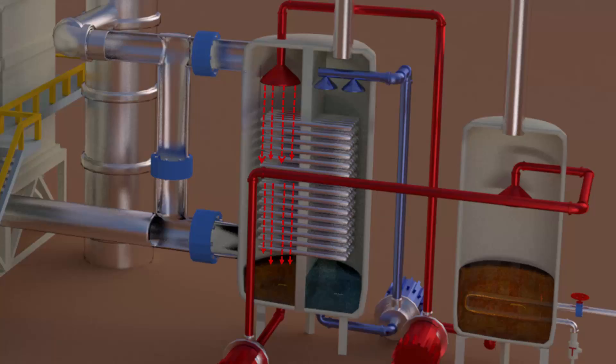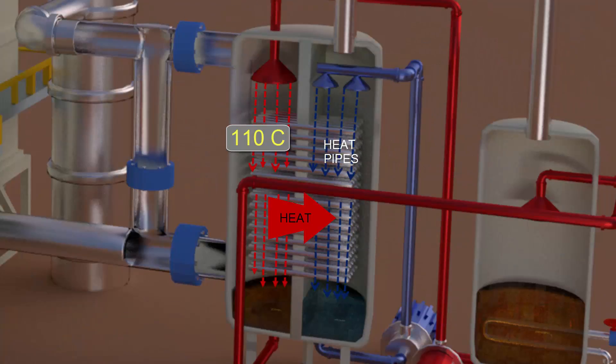In transitioning from gas to liquid, this water releases the latent heat of evaporation. A bank of heat pipes conduct that heat to the adjacent chamber. Here, pure water is circulated and sprayed over the other end of the same heat pipes.